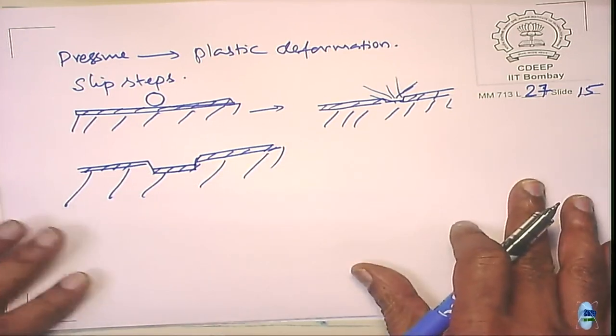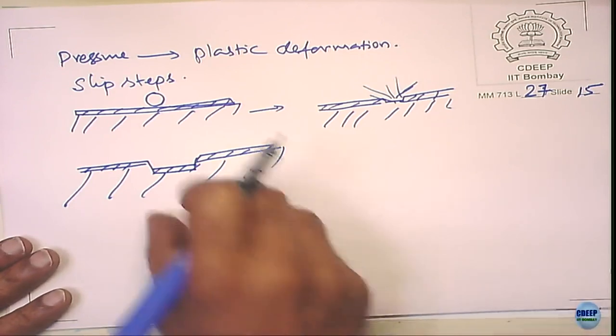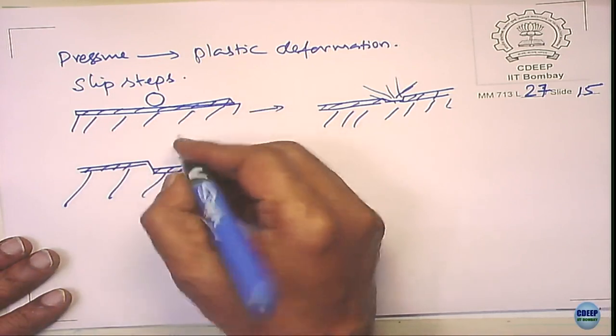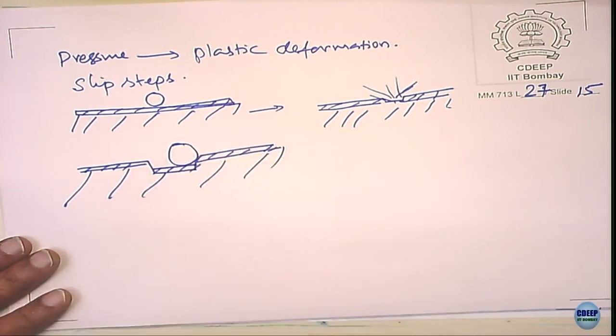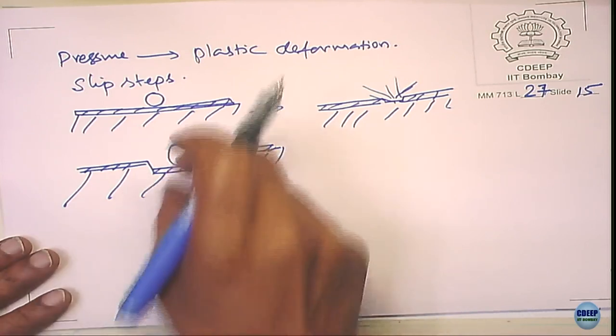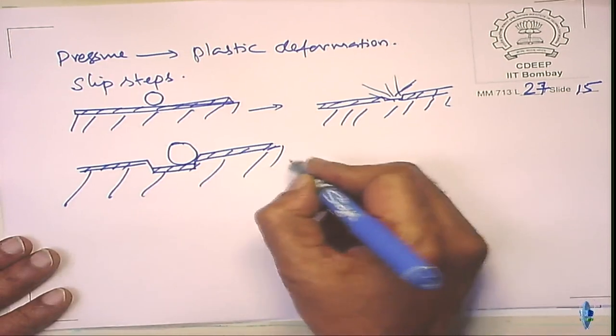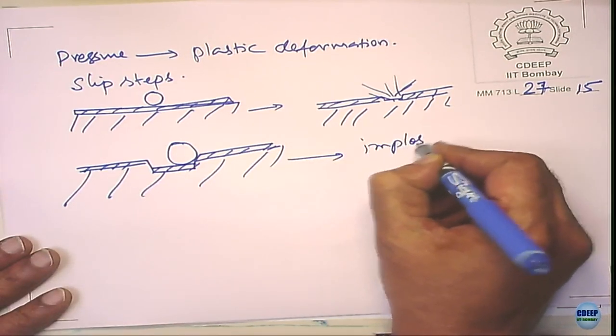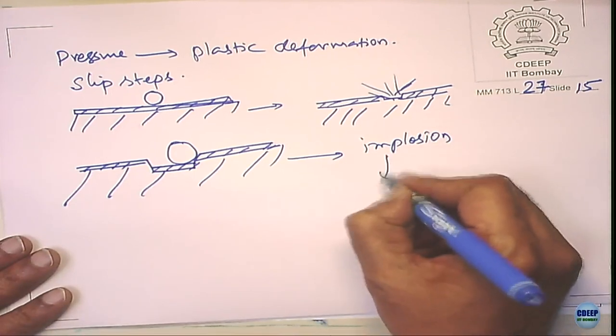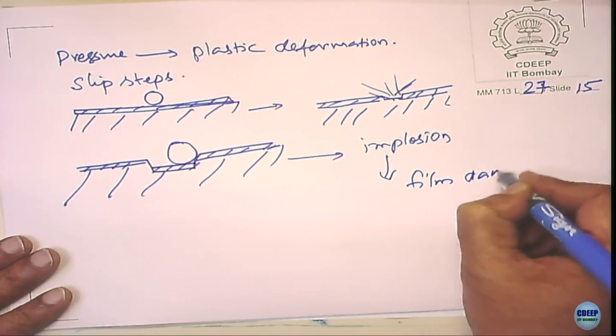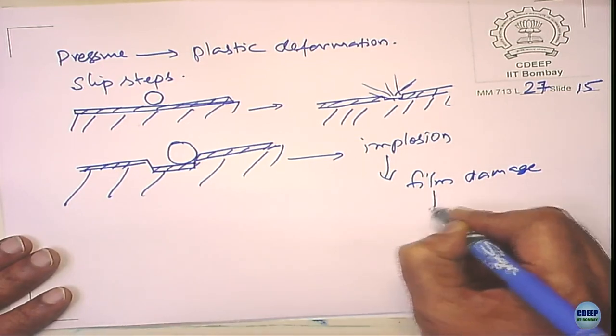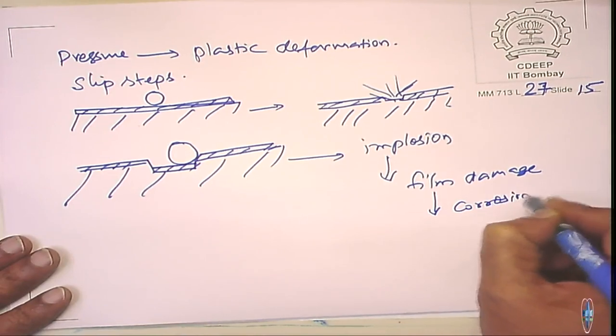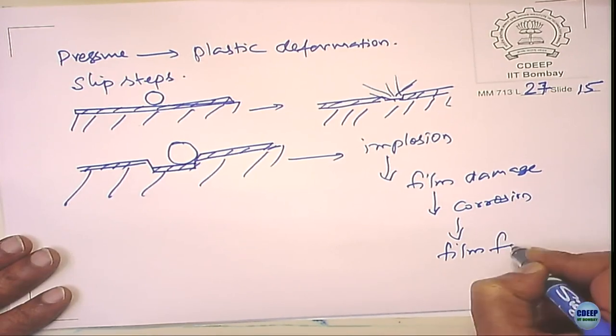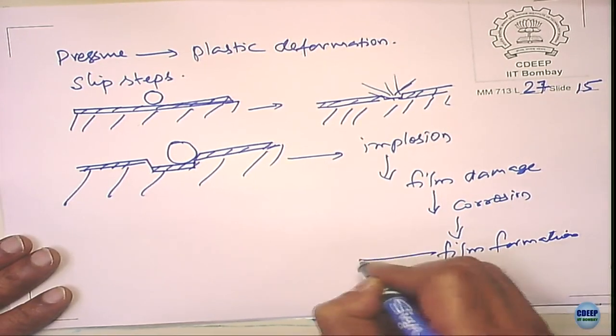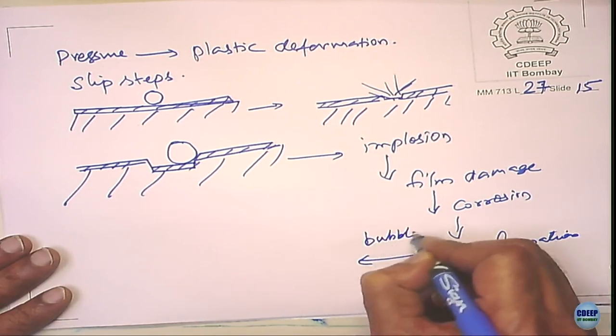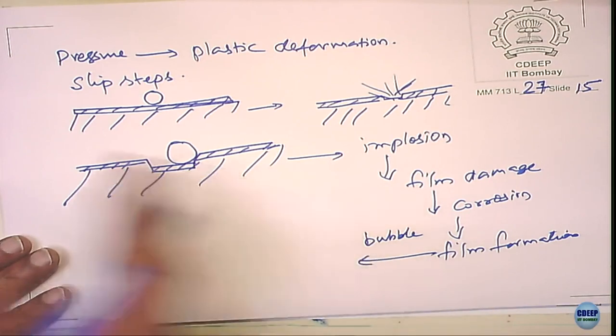Now, what happens is very interesting. The formation of the bubble here is much easier because it gives additional surface for the bubble to rest on. Then implosion happens, causing film damage. Then corrosion occurs, followed by film formation again. The process starts again, bubbles form on the surface, and this continues.